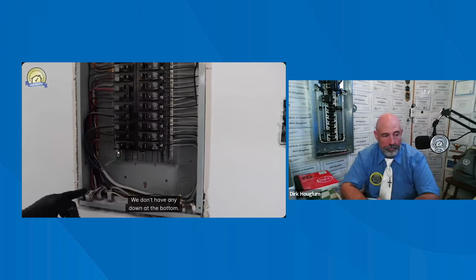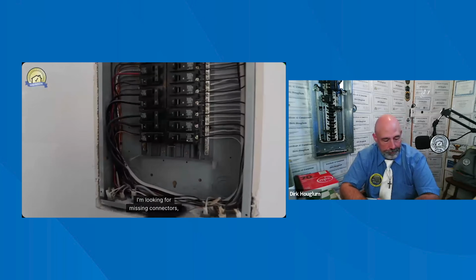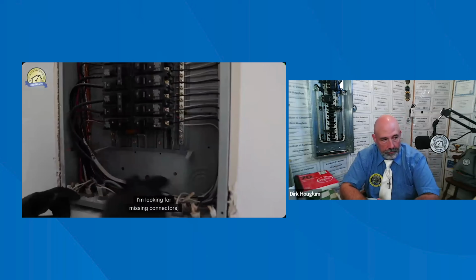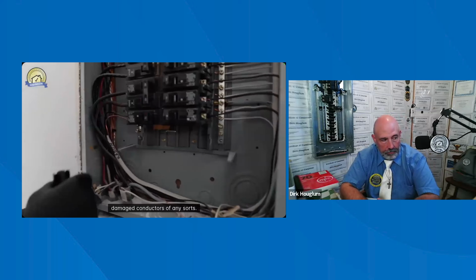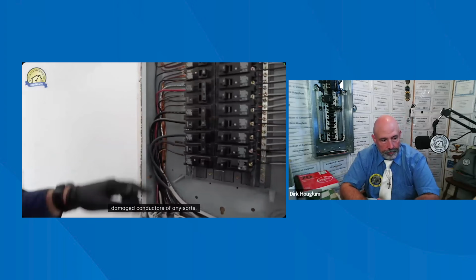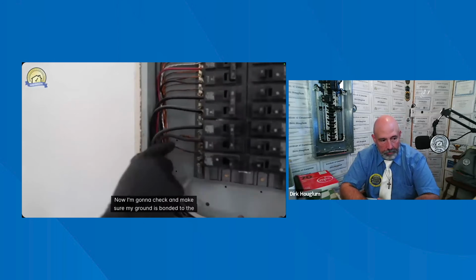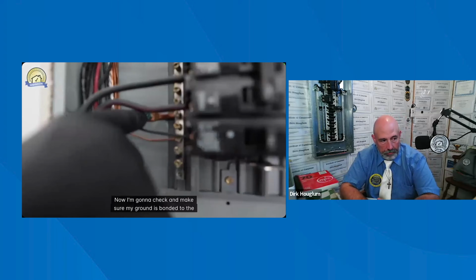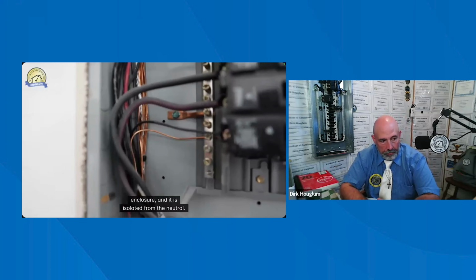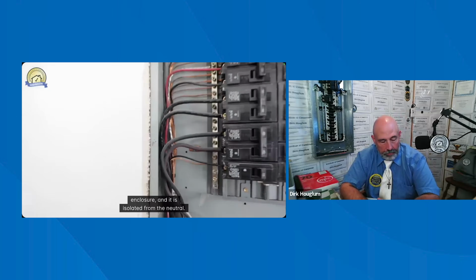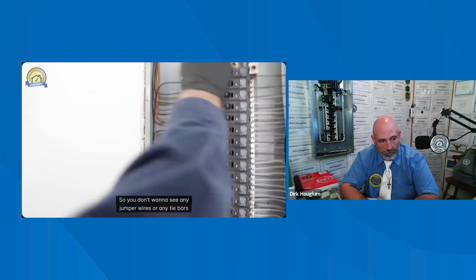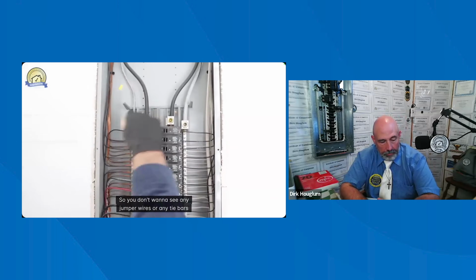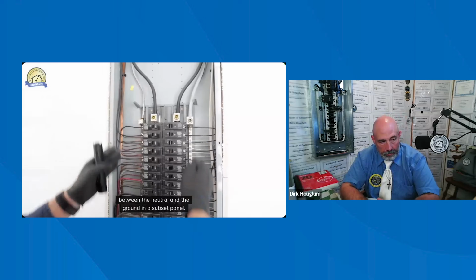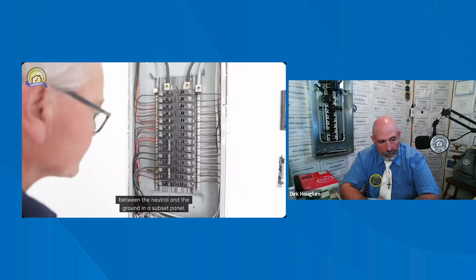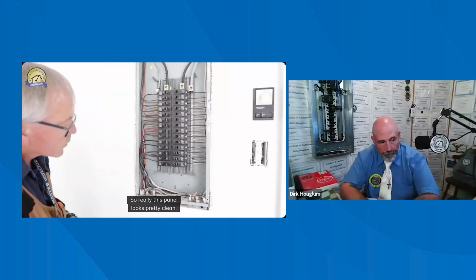I don't have any. Down at the bottom, I'm looking for missing connectors and damaged conductors of any sort. Now I'm going to make sure my ground is bonded to the enclosure and isolated from the neutral. So you don't want to see any jumper wires or tie bars between the neutral and the ground in a sub-fed panel. So really, this panel looks pretty clean.